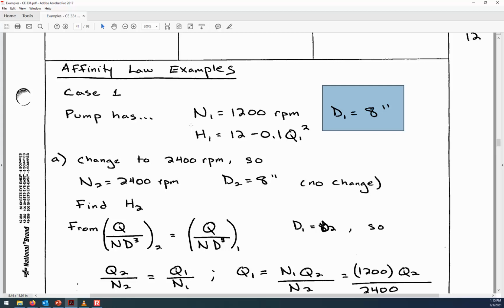So the pump head for the first pump is 12 minus 0.1 Q1 squared, where Q1 is the flow rate for that first pump.